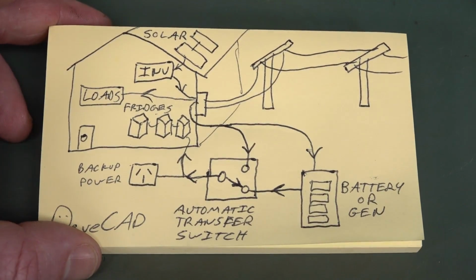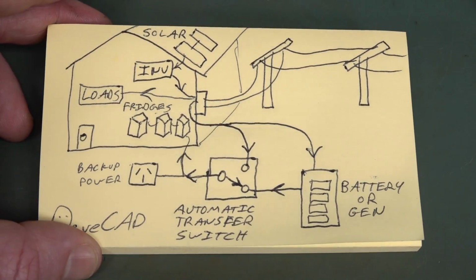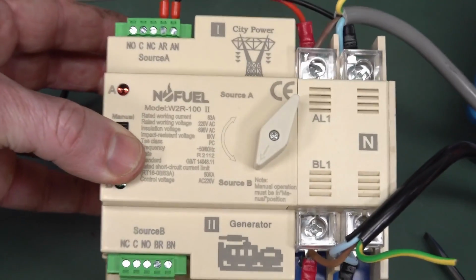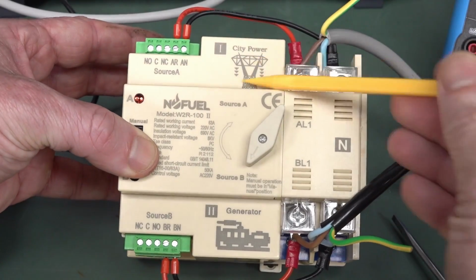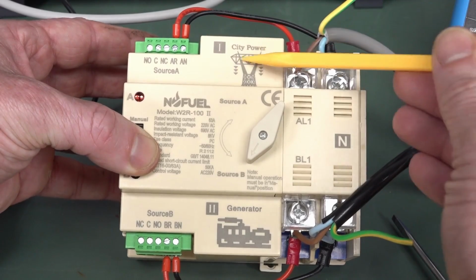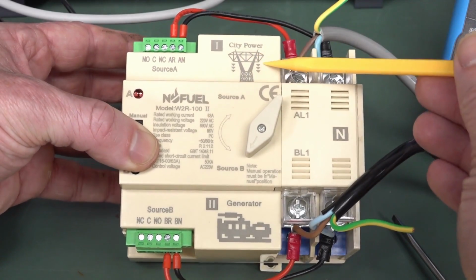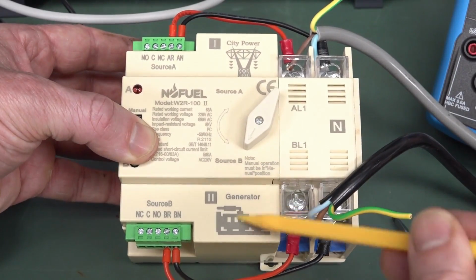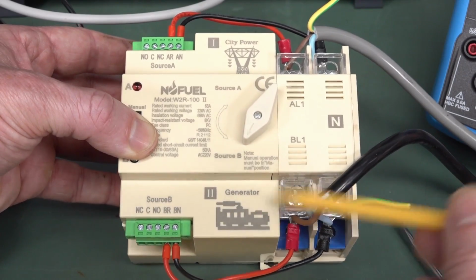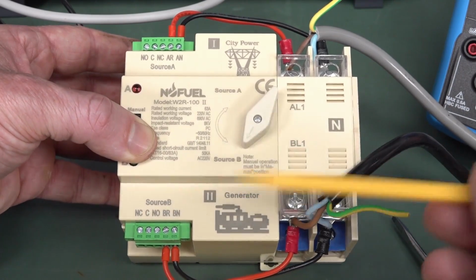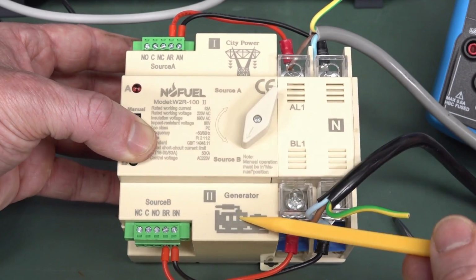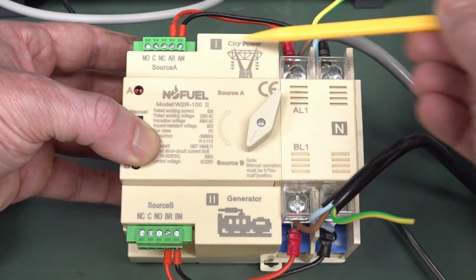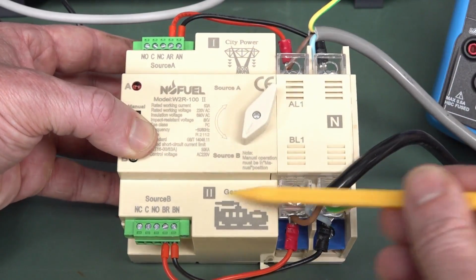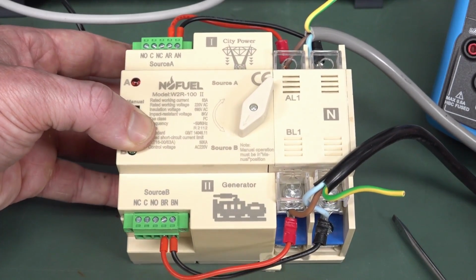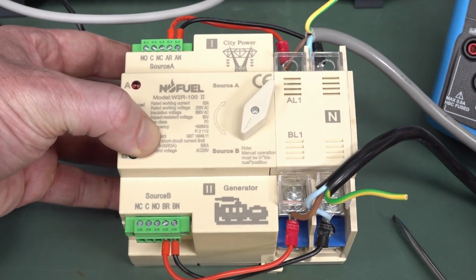They're very cool. But ordinarily you'd use them the other way around, as shown here: normally city power is the priority input, and only if the grid fails does your backup generator kick in. But I'm actually going to use it in reverse. I'm going to plug my battery into the priority input, which is normally for city power, and have the grid as my backup power. You can do that, it doesn't know the difference.